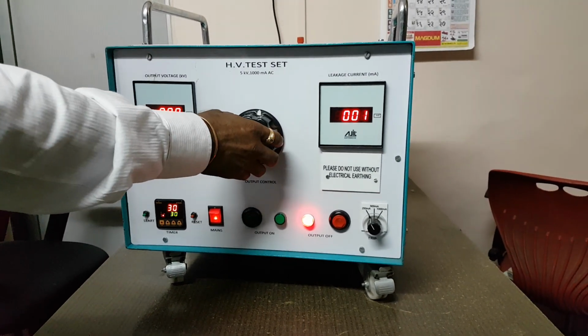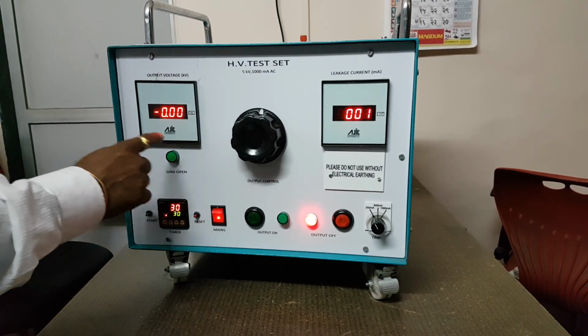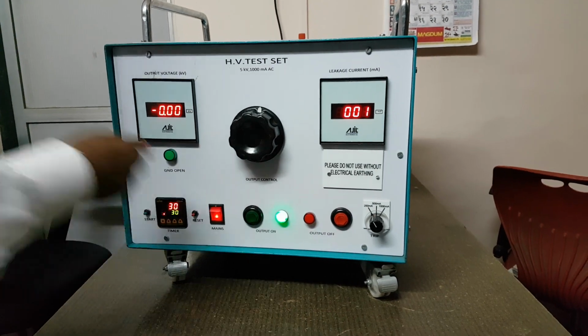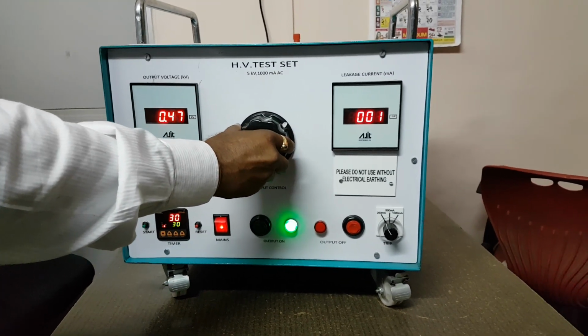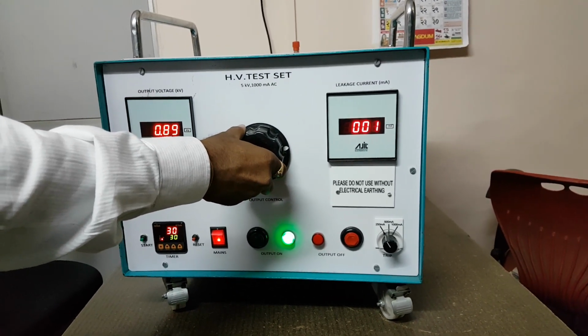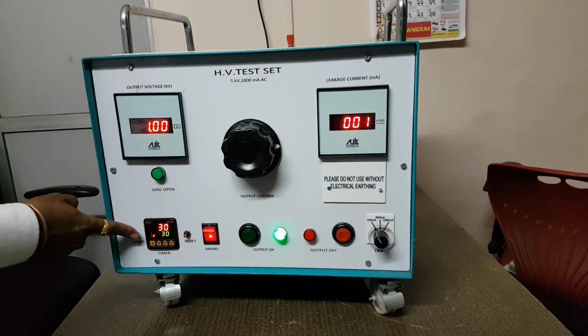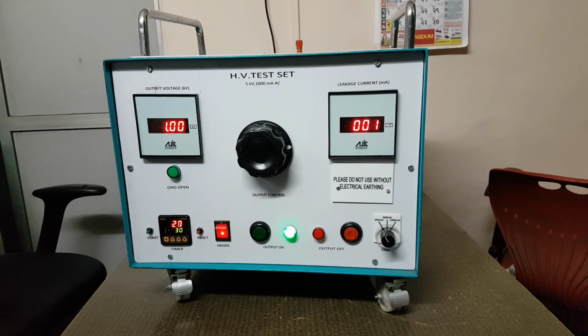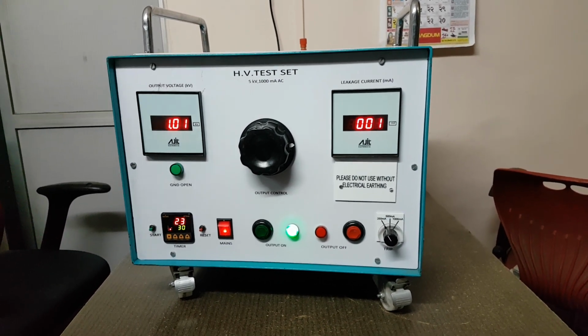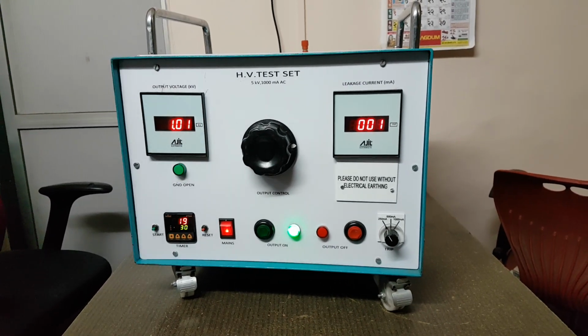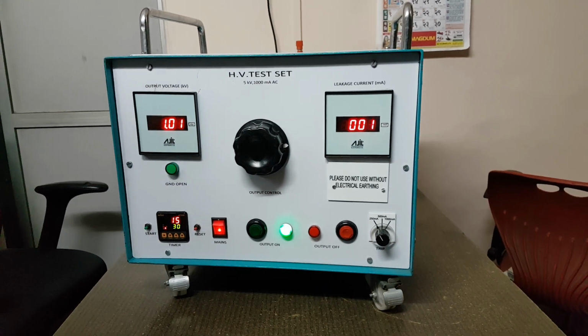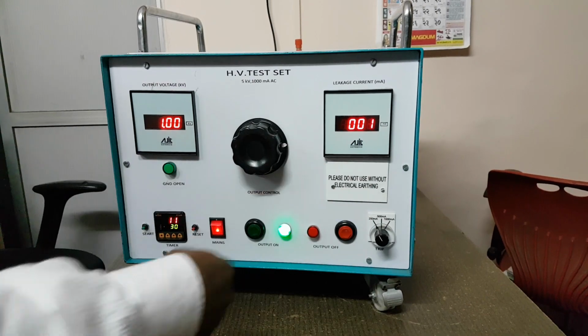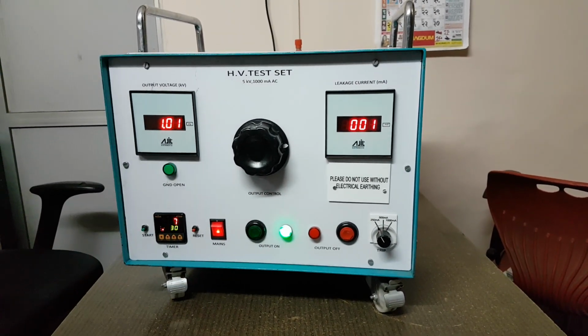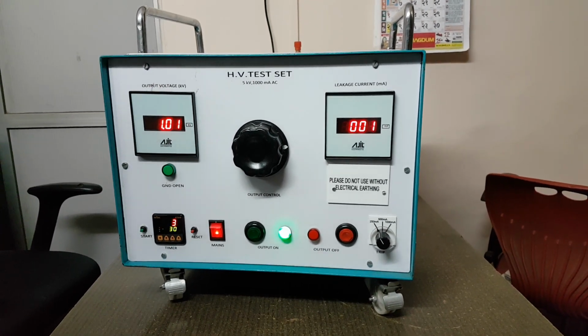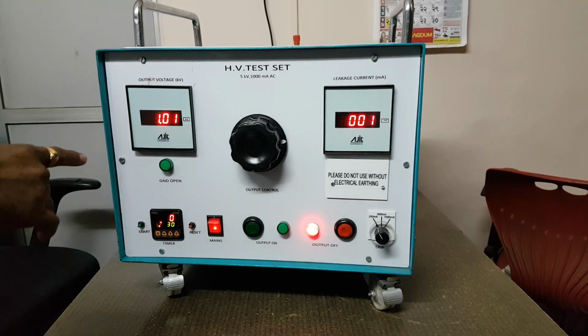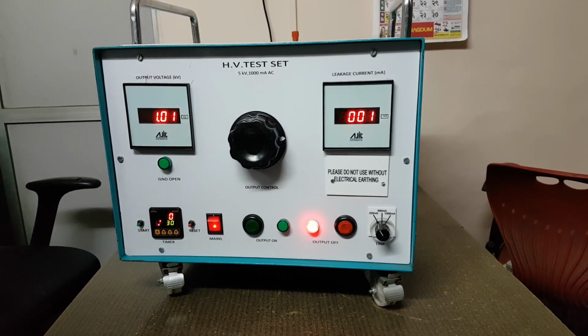Like if suppose we have to test the object for 1 kV for 30 seconds. This is the 30 seconds. We have to put the output on, set the output voltage to 1 kV as we desire, like this, and then start the timer. Now for this 30 seconds, the 1 kV output of this tester is applied to the object under test. If suppose due to the failure of the insulation the object fails, then a trip current flows and the instrument trips before the time has lapsed, then it is concluded that the test has failed. But if it stands and the time is completed successfully, like this, then you can conclude that the test has passed.